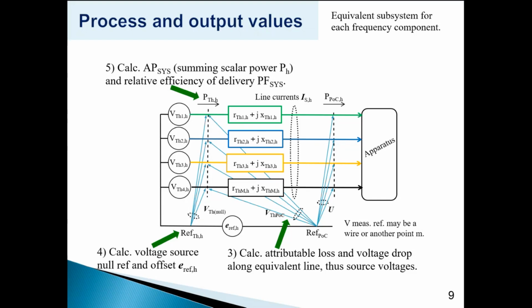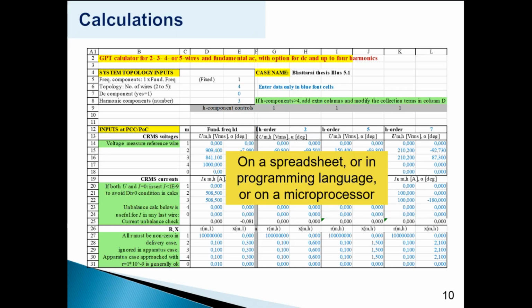And finally, we can allocate currents, the optimum set of currents in all those wires, depending on whether they are high resistance or low resistance, and the voltage source for each wire. And we can allocate the currents as the most efficient for delivering the power in terms of the delivery loss, the total delivery loss. For those of you who are mathematicians in your thinking, this is a transport optimization algorithm, where you look at the distribution of different pathways with a total cost in terms of losses or finance or something like that. And then finally, we can calculate currents for compensation if we put a compensator into the circuit. That's a very quick run through of the theory.